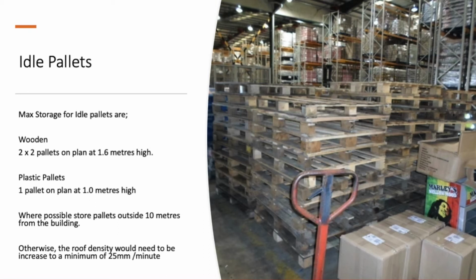2x2 pallets, so 4 pallets in plan, up to 1.6 metres high. That's it. Okay. When you get plastic pallet, it's 1 pallet up to 1 metre high. Okay. It is best, where possible, to store the pallets outside 10 metres away from the building. Otherwise, you actually probably need to increase the density at your roof to 25 millimetres a minute as a minimum.